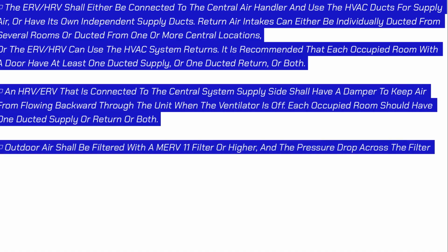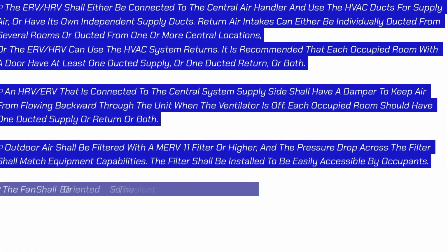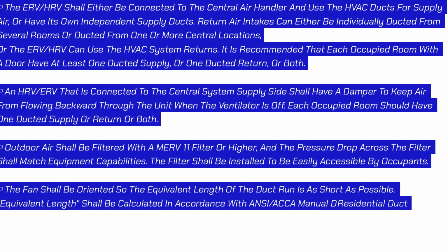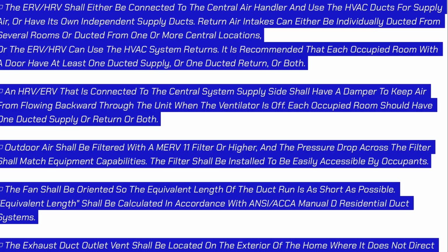Return air intakes can either be individually ducted from several rooms or ducted from one or more central locations, or the ERV, HRV can use the HVAC system returns. It is recommended that each occupied room with a door have at least one ducted supply, or one ducted return, or both. An HRV, ERV that is connected to the central system supply side shall have a damper to keep air from flowing backward through the unit when the ventilator is off. Each occupied room should have one ducted supply or return or both.